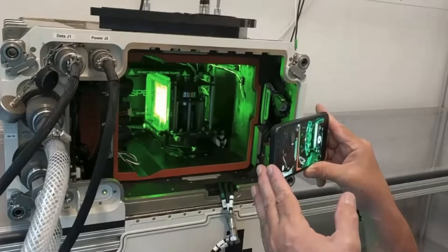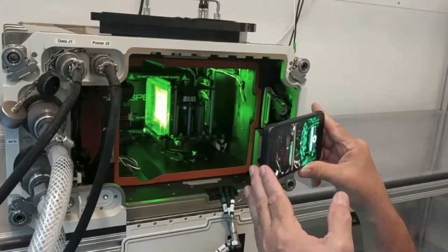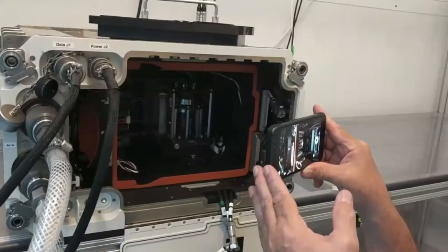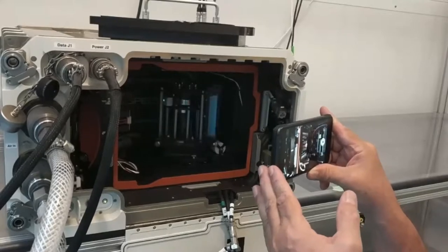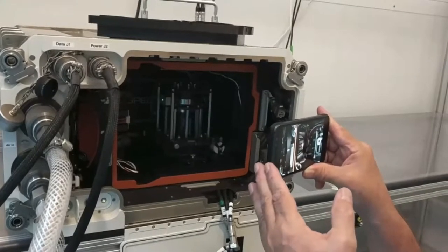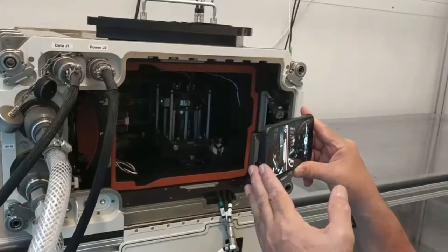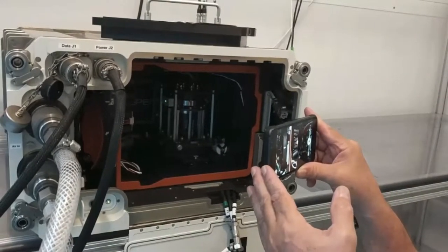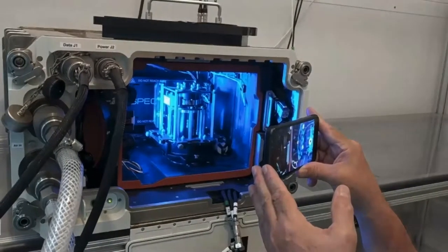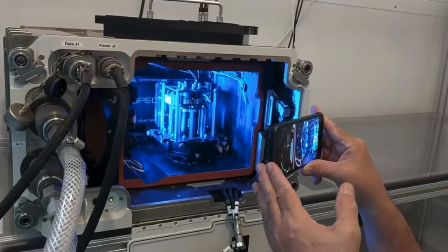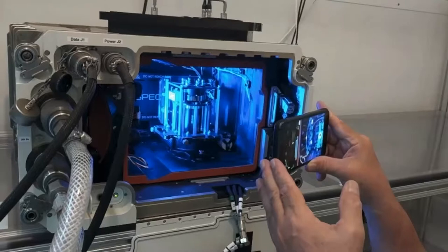Spectrum has a range of excitation wavelengths, GFP and RFP are shown here, allowing multiple probes to be imaged in one sample. The carousel rotates the Petri plates in succession to the position for imaging. The chamber is a controlled environment with a CO2 scrubber, thermoregulation, and grow lights above the Petri plates to support photosynthetic growth. This environment allows multiple days of imaging while the sample grows in microgravity.